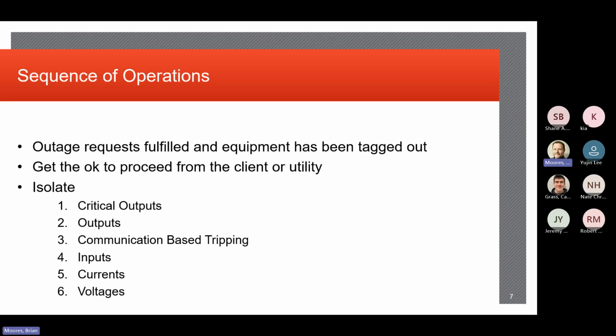The current is going to spike. So if I went up to a relay and opened up a voltage first, relays are smart enough probably to realize it's not a fault, but in the older relays, not the case. It could actually look like it would lose a voltage, and now you've got an impedance measurement, it could fall within the zone of protection, and it could trip. So that's why voltages are last on that. We used to call it voltage restraint in the old days, testing old relays, because it was actually the voltages that would physically restrain the inductive devices that were in the old electromechanical relays.